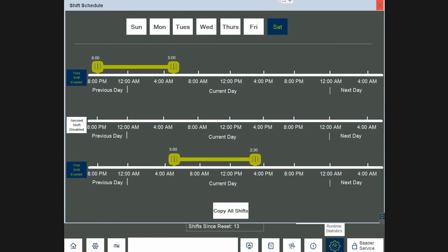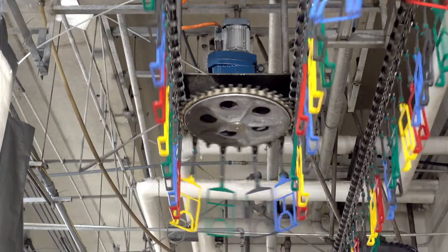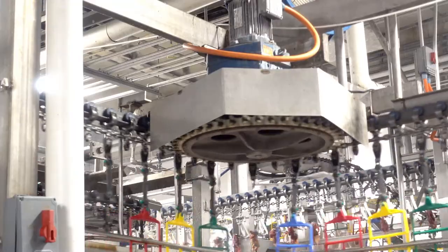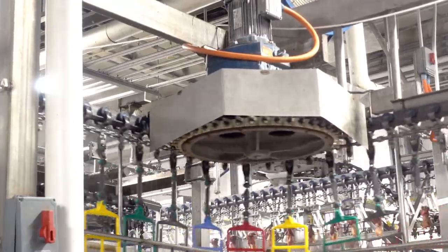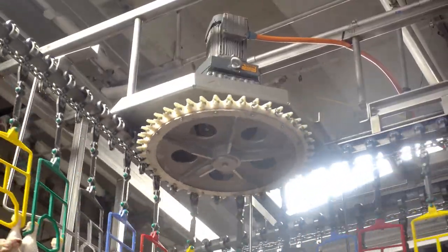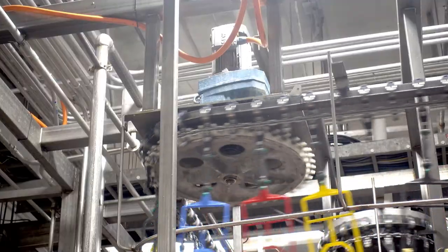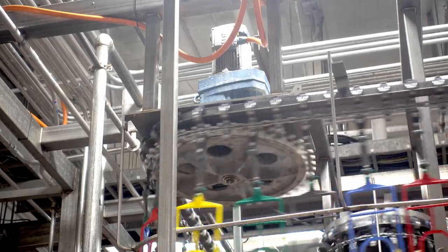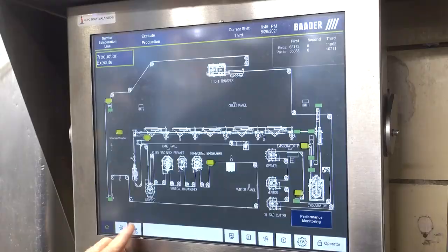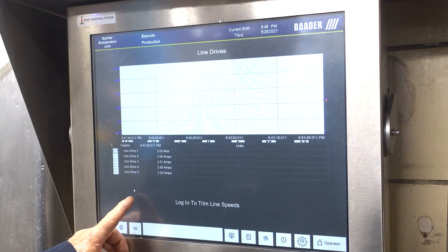Shift schedule allows operators to customize shift times each day of the week. Line drives that move the overhead conveyor are customized for each installation based on numerous factors such as line speed, line length, and bird size. These drives must work together for optimal line efficiency. The Baader control system graphically displays the amperages of each line drive to aid in troubleshooting issues.